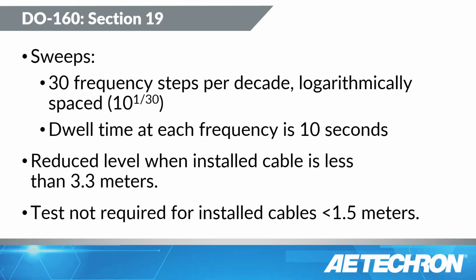Now, once again, we're going to perform frequency sweeps over defined frequency ranges. They're going to be 30 frequencies per decade, logarithmically spaced. The dwell times are actually 10 seconds per frequency. So some of these tests can be a bit faster, and many of these frequency ranges are much shorter than they are for Section 18. So testing may be in the realm of 5 to 10 minutes or so.